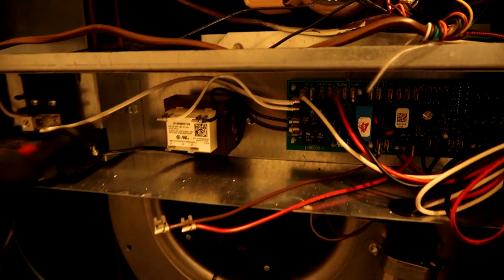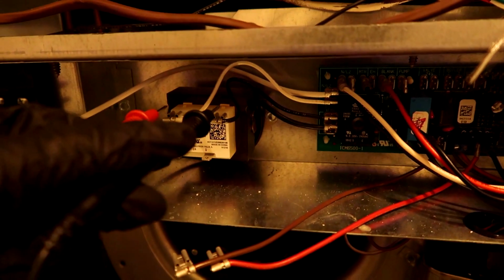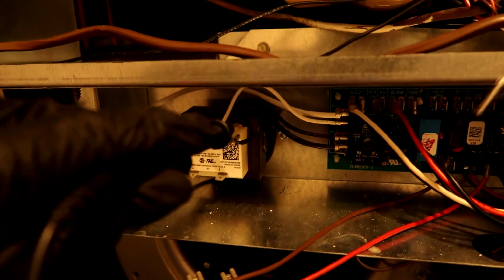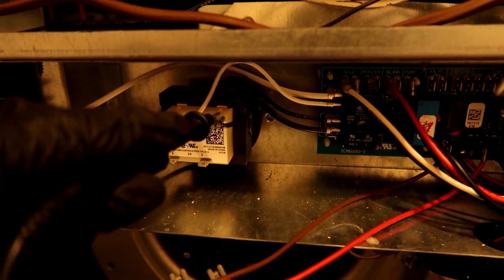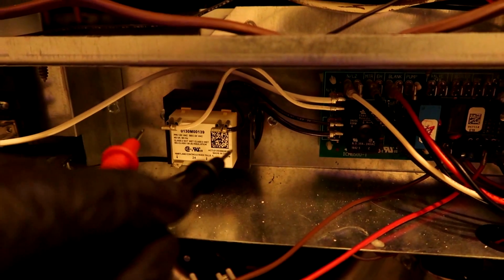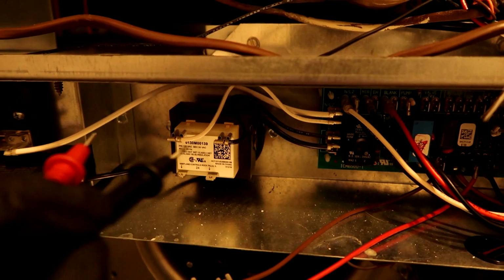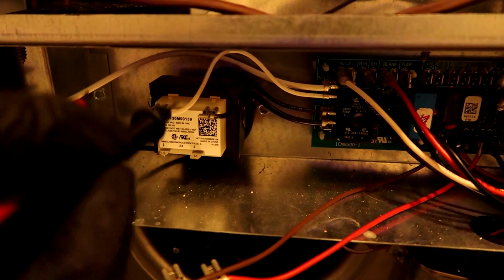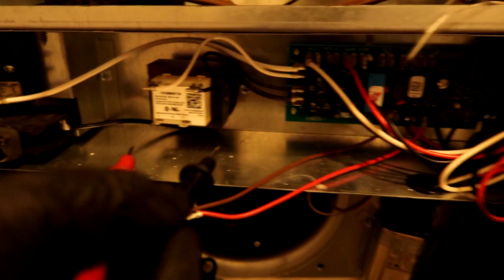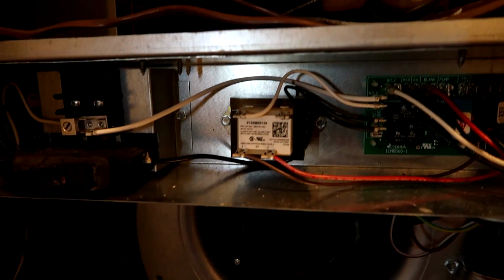So for you new guys, all HVAC is high voltage controlling low voltage. It comes in from the breaker here at high voltage, 240 or 120. Then the transformer transforms it, hence the name, no pun intended, into low voltage, and it comes out, and that's what powers your low voltage, your thermostat and everything. Alright, transformer hooked back up. Fuse is good. Come on, big money, no whammy.